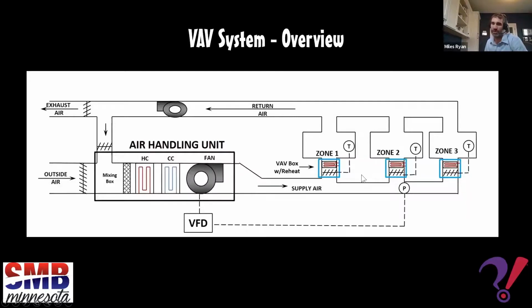So if they all start closing because they're all satisfied and they don't need as much cooling, the pressure in the supply air duct is going to increase. If it starts to increase above a set point, then that information would be relayed back to the air handling unit. The air handling unit would say, geez, the pressure in the supply duct is rising above set point. That must be an indication that dampers are closing, and therefore I could probably slow this fan down because I don't need to push as much air as I'm currently pushing. And in turn, a variable frequency drive would be used to slow down that fan to track the static pressure on its respective set point. So that's a VAV system.